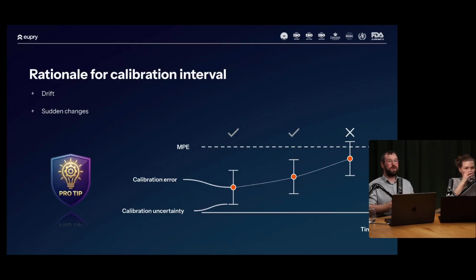I do know that in a lot of places, it has been put into your own system, or it's been put into auditors' mindsets that sensors, temperature sensors, must be calibrated yearly. And if that's the case, go with that. But technically, there's no reason why you should not be able to extend it. And sometimes you can do it. Let's say, oh, we've had this equipment for years. It has drifted by so and so much. So we expect to extend the calibration period just a little bit.